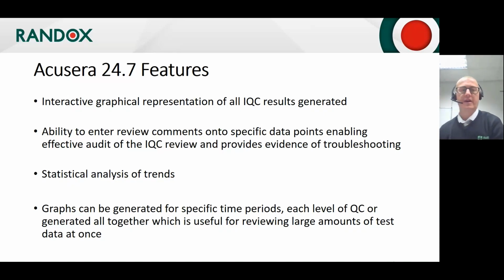You can do statistical analysis of trends with some of the reports and from the graphs themselves. So you can look over time and see where your QC is trending to, where it's coming from. You can pick up if there's been issues such as wrong lot number put on the analyzer. The graphs can be generated for specific time periods, so you can narrow it down to 1 or 2 days, or you can look at 2 or 3 months, or when you get assessed, you can pull up a year's worth of data for your friendly assessor to look through.